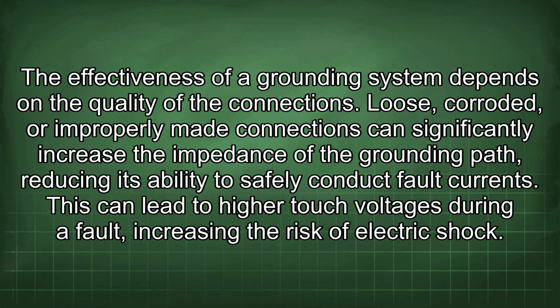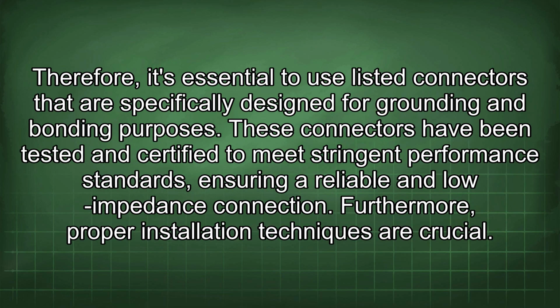It is important to carefully review and follow the requirements of the NEC to ensure that electrical systems are properly grounded. The effectiveness of a grounding system depends on the quality of the connections. Loose, corroded, or improperly made connections can significantly increase the impedance of the grounding path, reducing its ability to safely conduct fault currents. This can lead to higher touch voltages during a fault, increasing the risk of electric shock. Therefore, it's essential to use listed connectors that are specifically designed for grounding and bonding purposes. These connectors have been tested and certified to meet stringent performance standards, ensuring a reliable and low impedance connection.